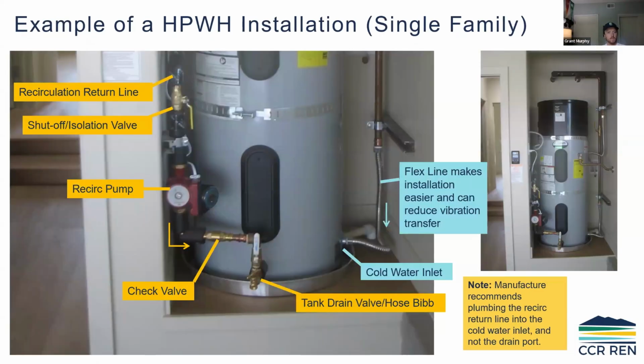So this is where we're saying, hey, do not plumb your recirculation pump into the tank drain valve hose bib. That's explicitly not allowed in multifamily, but in single family the language didn't get put in there, and so we are seeing plumbers do this. Really, that return should just be plumbed into the cold water inlet line, that's where it should go. The reason is because of how the bottom of the tank and the tank valve hose are designed.